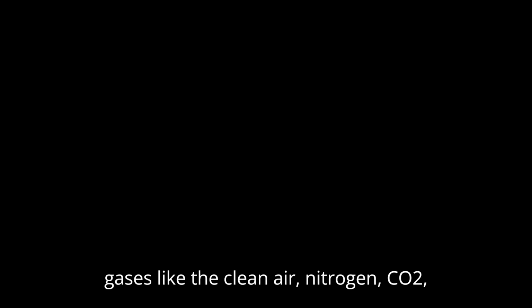Got it. And the FMT 400 series comes in a couple of flavors. Right. There's the FMT 400 VTS. That's your standard model for general process stuff: compressed air systems, chemical processes, air separation plants, even handling hydrogen flow. And the FMT 400 VTCS. The CS suggests something different. Hygienic. That's for food and beverage. Same principle, but built with materials and connections suitable for sanitary applications. Think smooth surfaces, specific fittings like DIN 11851. For gases like clean air, nitrogen, CO2, or oxygen used in food processing and packaging.